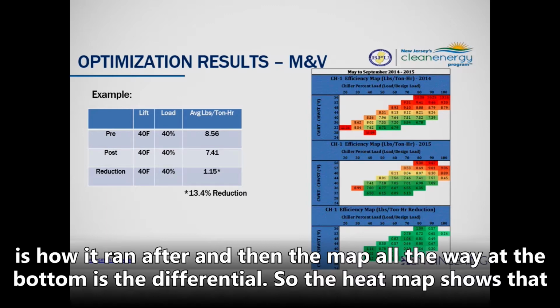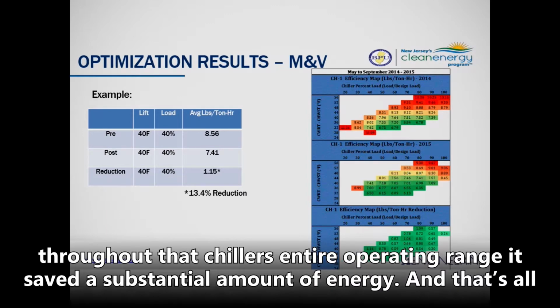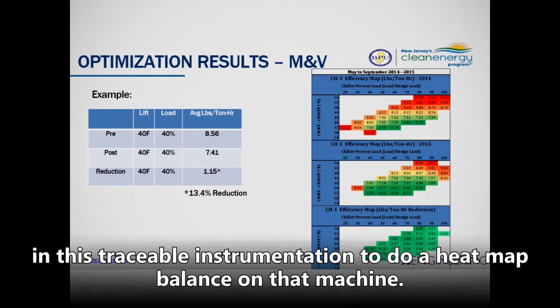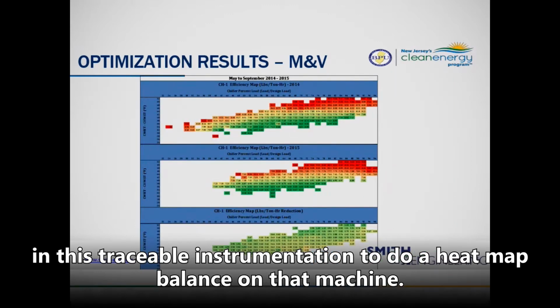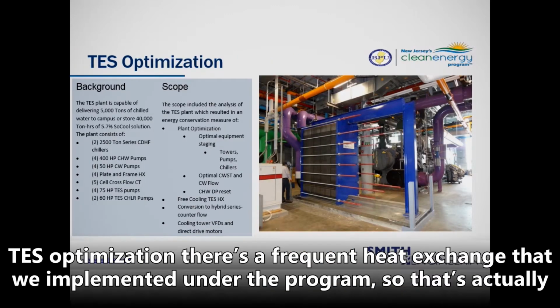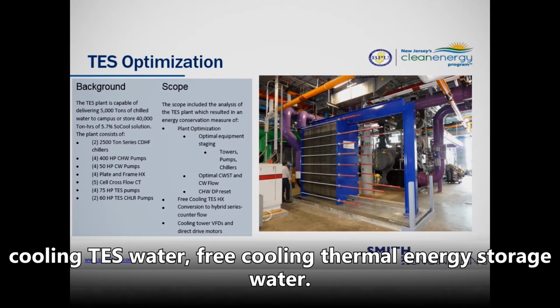So the heat map shows that throughout that chiller's entire operating range, it saved energy, and a substantial amount of energy. And that's all NIST traceable instrumentation to do a heat mass balance on that machine. TES optimization, there's a free cooling heat exchanger that we implemented under the program. So that's actually cooling TES water, free cooling thermal energy storage water.